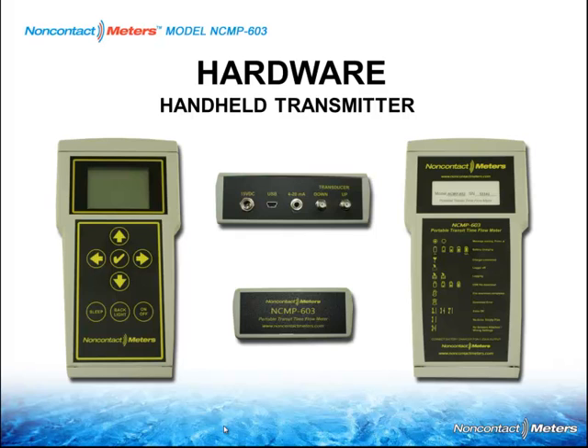This particular device, as we said, is designed for applications that are clean liquids, things that are less than 2% suspended solids, aerations, or solids. You can program the device to read in English, French, and Spanish. The electronic enclosure is ABS plastic. It is not a weatherproof enclosure, so you need to put it in the big suitcase if you need to leave it out in the mud. It has a big bright display, which even I can see with my glasses off. The outputs are 4 to 20 milliamp. As I said, it does have a logger, and it does come with a piece of software for the logger. The operating temp for the handheld electronics is, on the traditional side, -5 to 140 degrees F, and on the metric side, -20 to 60 degrees C. And the plastic carrying case itself, the suitcase, is rated to IP67 with foam inserts.